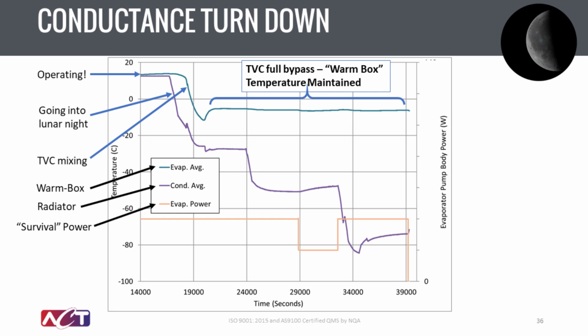Here's a little test plot we did in the lab here to verify the conductance turndown. The simple demonstration here on the top left, you can see that the evaporator average and condenser average, so that would be the warm box to the radiator, are very close in operating temperature. That means that the loop is picking up that heat and bringing it to the radiator and rejecting it very efficiently with that tight temperature range. We then were using liquid nitrogen on that radiator and dropped the temperature down as would occur at lunar night. And you can see that as the thermal control valve temperature began to drop, the temperature of the evaporator and condenser moved further and further away from each other.